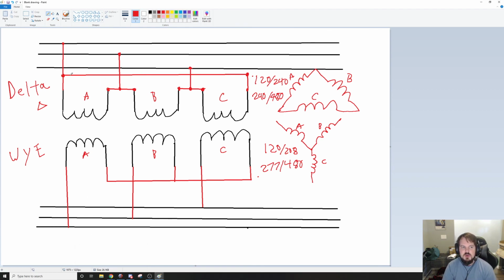A primary Y won't have a neutral connection, but a secondary Y will have a neutral connection. There isn't a way to get a neutral connection on a delta without splitting one of the coils, the bottom coil, and making what they call a center tap delta. But with a Y, it just naturally forms a neutral. That's why we have so much 277 volt lighting or 120/208, because if you have a three-phase system, the easiest way to get a neutral is with a Y.